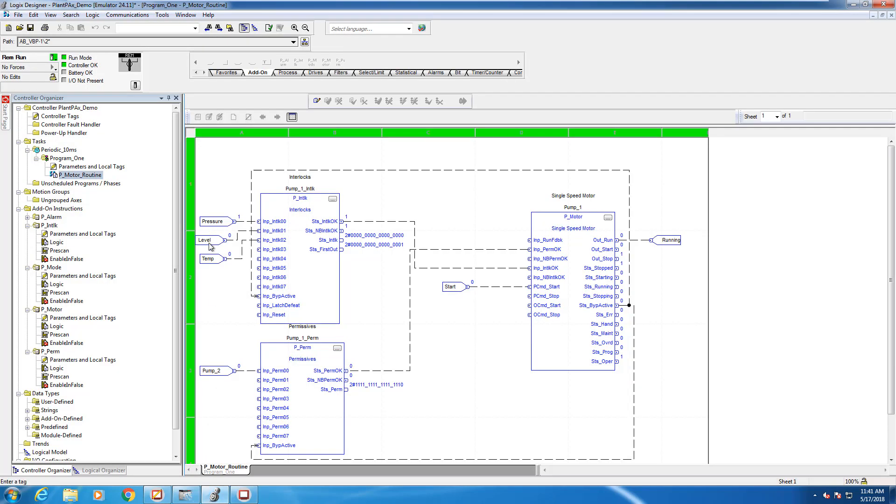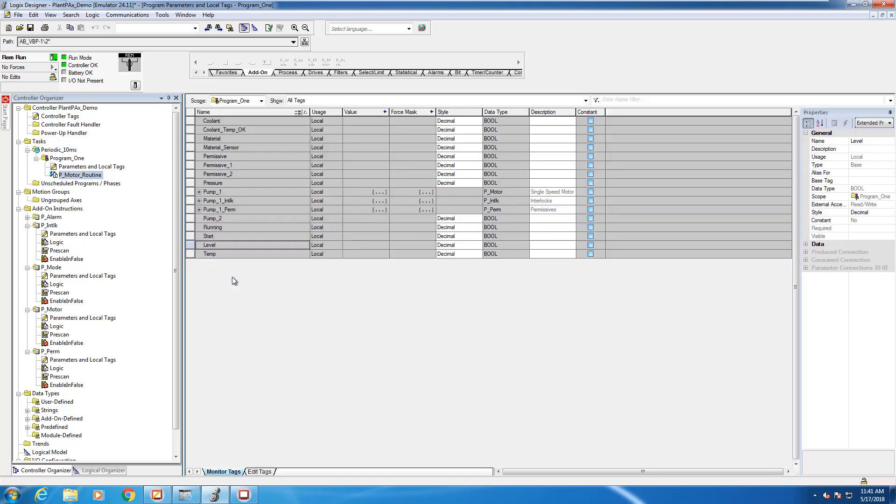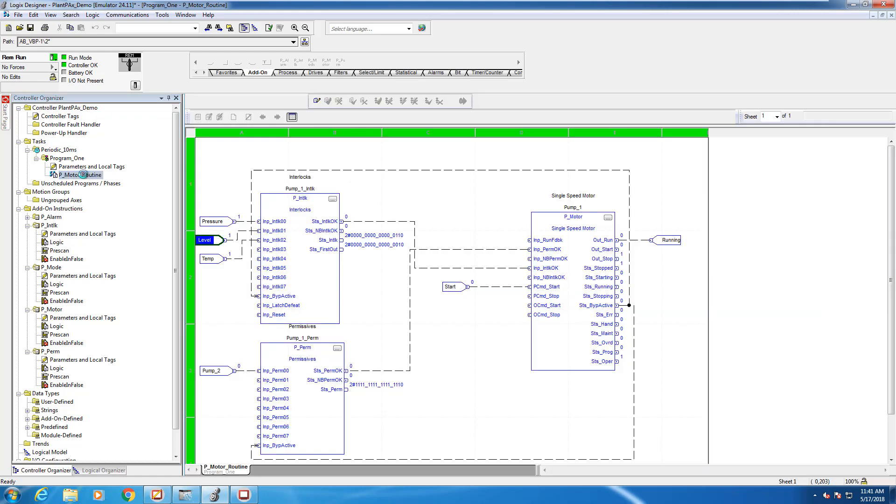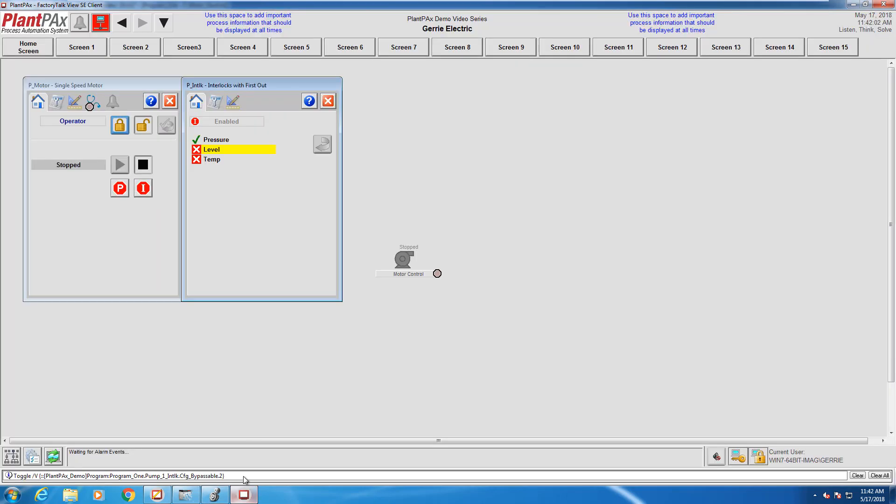Let's go back to our program and change the state of one of our conditions and see how the interlock reacts. I'm going to toggle the states for level and temp, and then we'll head back to the HMI and see how the system responds. You can see here from the interlock faceplate it shows that level was the first condition to trip on this interlock.